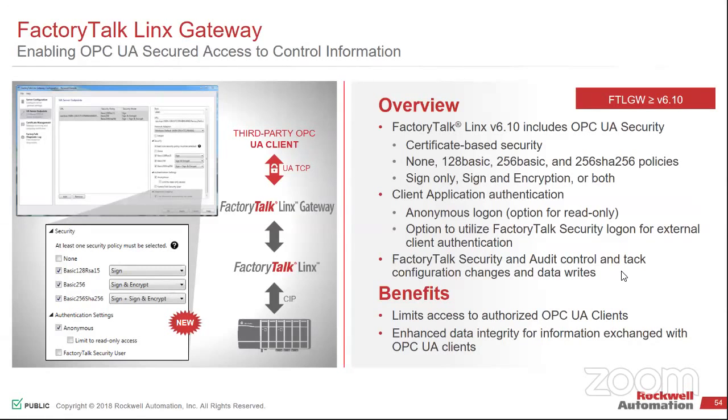Yeah, because at that point, if we needed to go faster, we still have the Softing option on third party, and that's a hardware-based solution. That might be something if we needed to do OPC UA at, let's say, 50 milliseconds, I think we would go down that route. But if we needed to do something at a standard Windows rate that we're able to pull from the HMI side of it, we end up using this.